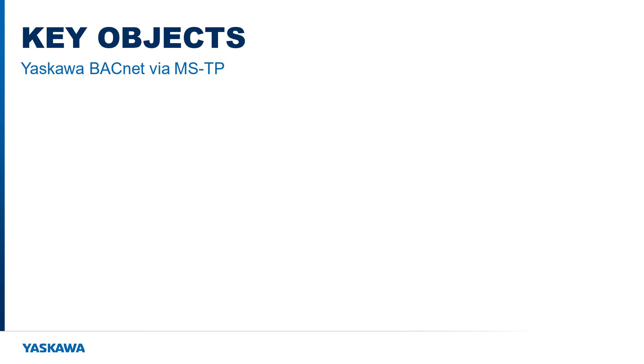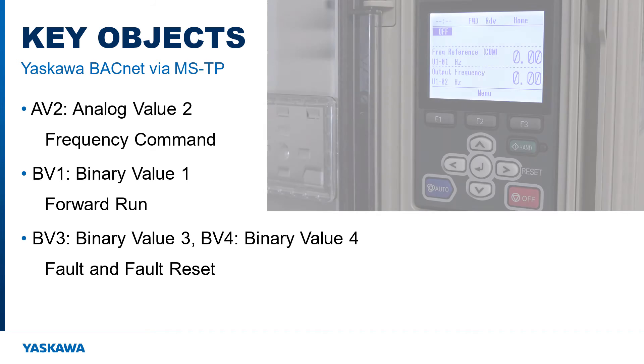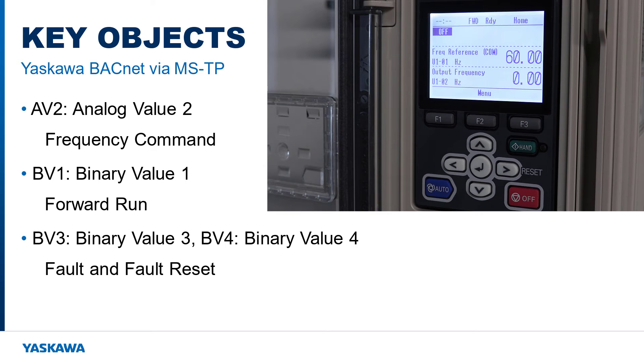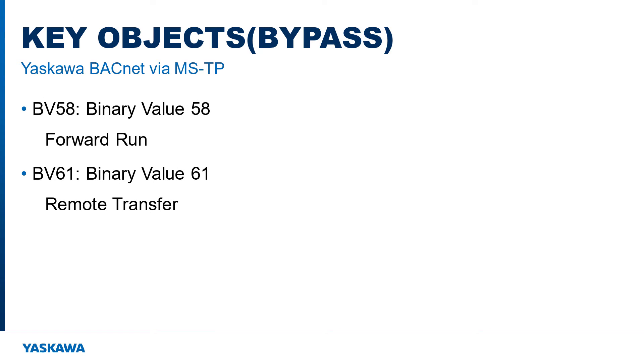Some examples in the standard objects for the drive include AV2 (analog value 2), the frequency command which sets a speed reference to the drive via the BACnet network. BV1 (binary value 1) gives the forward run command to the drive. BV3 and BV4 set the external fault and fault reset. Some bypass examples include BV58 and BV61, which give the bypass a forward run command and a trigger to transfer the drive to bypass, respectively.